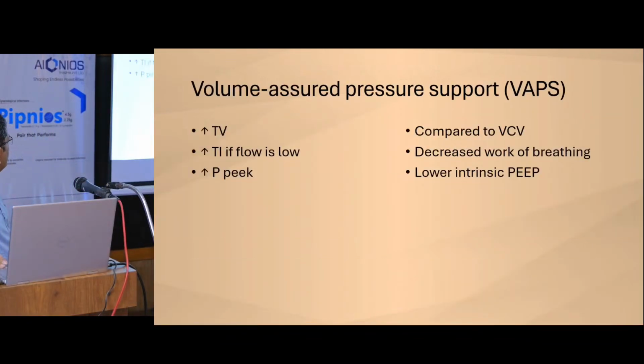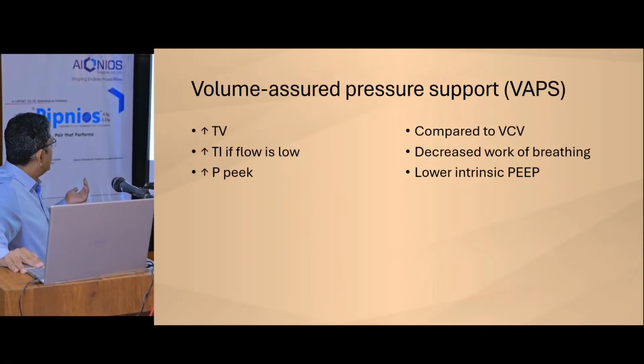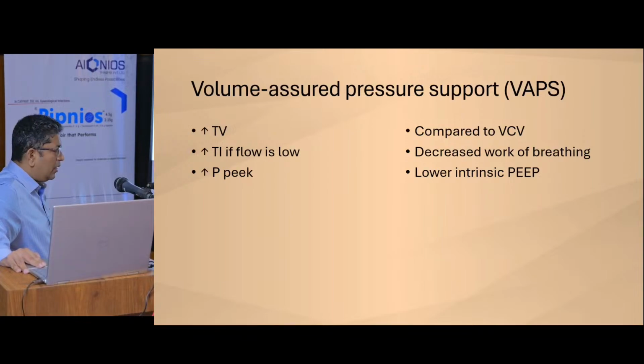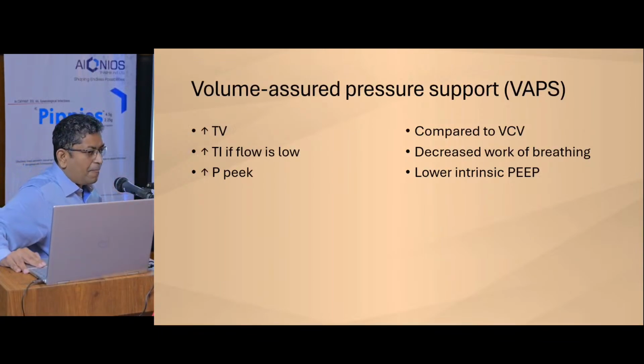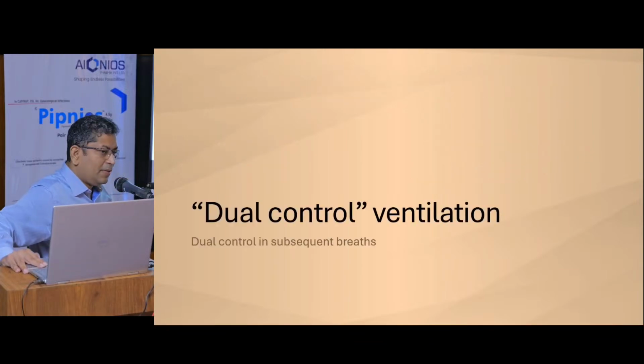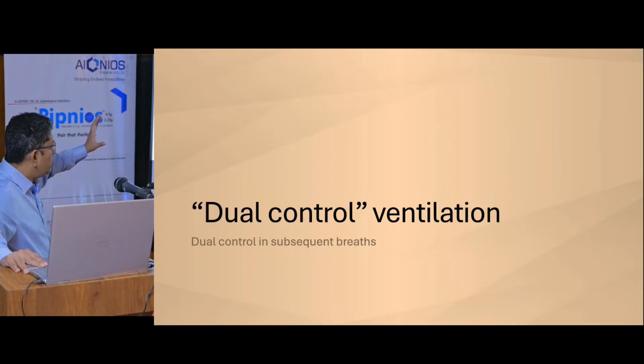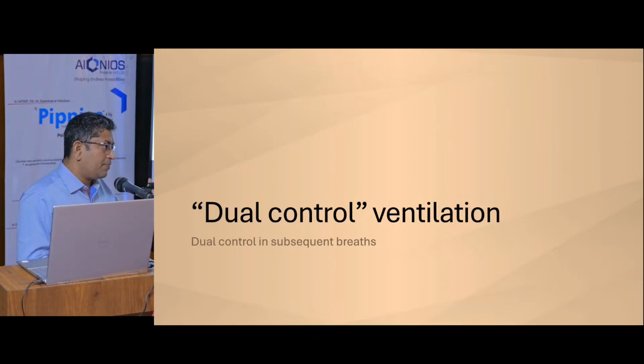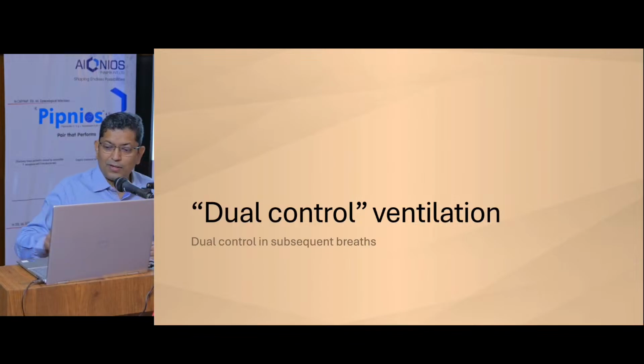So you get better when you compare this thing with pressure control. Maybe you have a better tidal volume. Increase inspiratory time if the flow is low, and there will be higher peaks. So unfortunately, the problem is it's not very good for synchrony. So you go to dual control ventilation, dual control in subsequent. Okay, these are much more interesting ones.